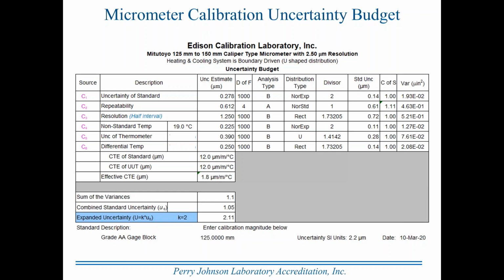You can record the non-standard temperature that existed when you performed the calibration and plug in those known pieces of information, the 5 measurements that you took, and it will calculate the experimental standard deviation of the mean. And then it will populate all of the budget to the right, filling in all that. Once the last one is filled in, it will do the calculations at the bottom and give you the measurement uncertainty of this micrometer when calibrated at 125 millimeters.